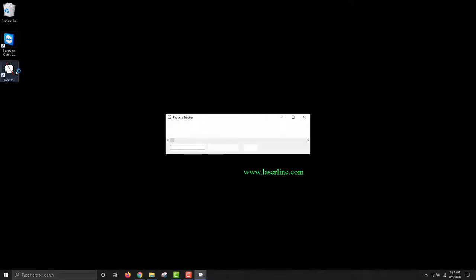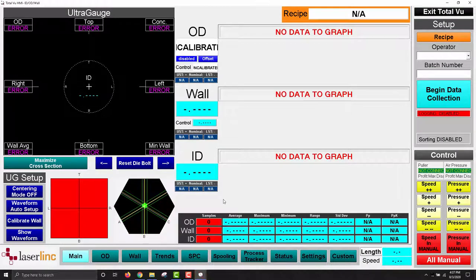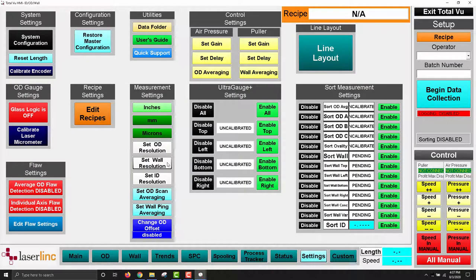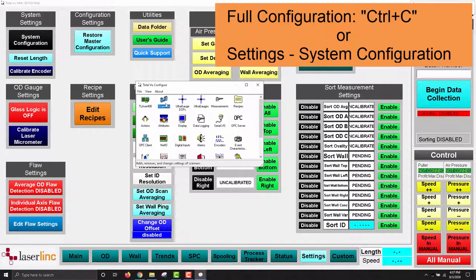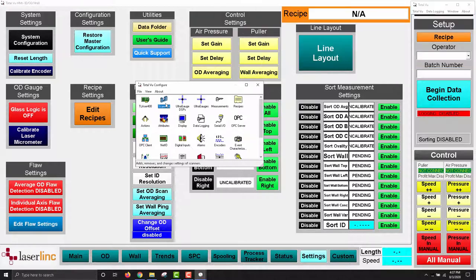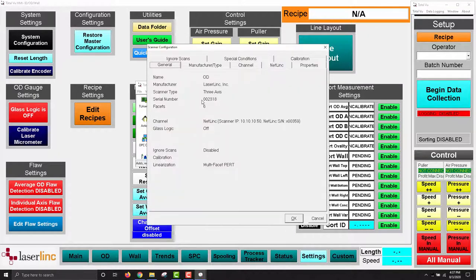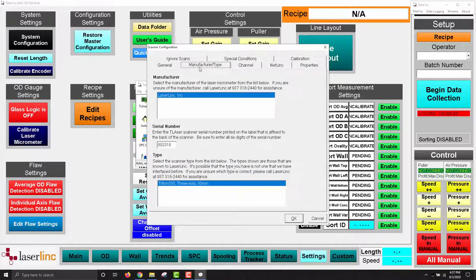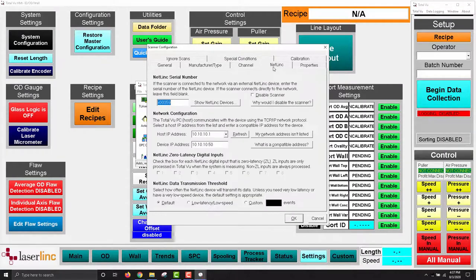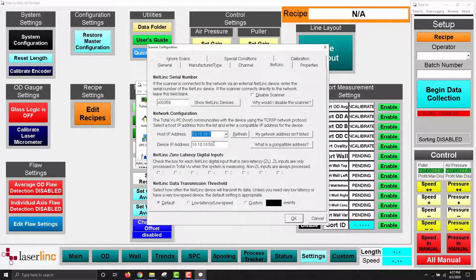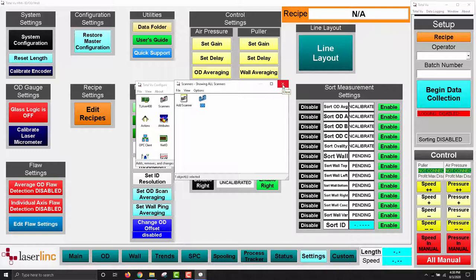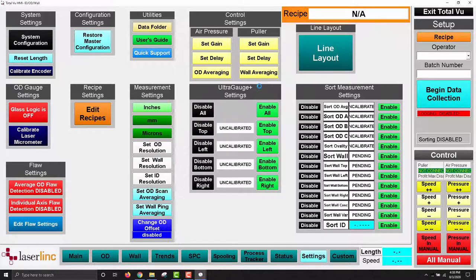Now, open TotalVu by double-clicking on the TotalVu desktop icon. We will use TotalVu to verify that the new equipment is able to communicate with the computer. We'll start with the micrometer. On the keyboard, press Control-C to open the full configuration menu. Double-click on the gauge icon, then click on the icon of the predefined micrometer. Ensure that the serial number entered in the software matches the serial number listed on the laser micrometer. Navigate to the NetLinc tab and verify that the host IP address is set to the static IP address assigned to the computer's network port. Verify that the device IP is a static IP address that is compatible with the host IP. This will ensure that the gauge is on the same network as the computer.